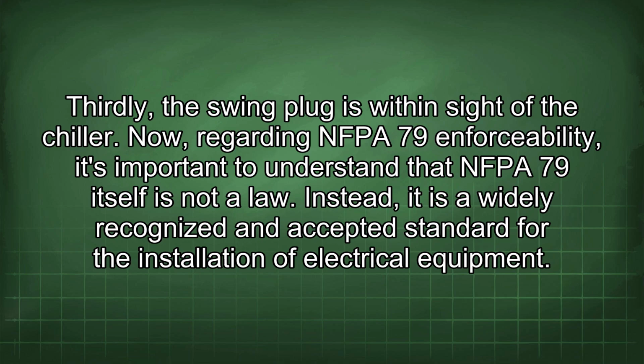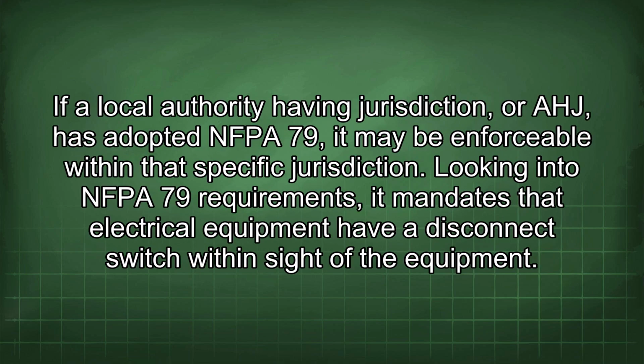Now, regarding NFPA 79 enforceability, it's important to understand that NFPA 79 itself is not a law. Instead, it is a widely recognized and accepted standard for the installation of electrical equipment. If a local authority having jurisdiction, AHJ, has adopted NFPA 79, it may be enforceable within that specific jurisdiction.